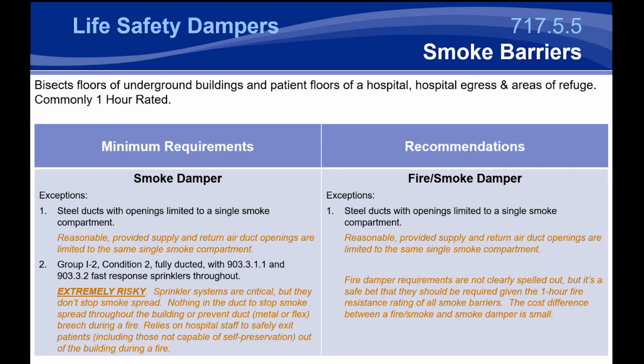We think this is incredibly risky due to the overall size of the smoke compartment. It's, I believe, 60,000 square feet, which could be the entire occupancy. And it's really relying on the sprinkler systems to work and potentially your fans exhausting smoke out of the affected area. So if any of those systems fails, you're going to have the potential for smoke to spread, because even though your sprinkler systems are critical and they're putting out the fire, they're not stopping the smoke from spreading. They're actually creating a source of smoke. So there would be much more smoke that needs to get exhausted.